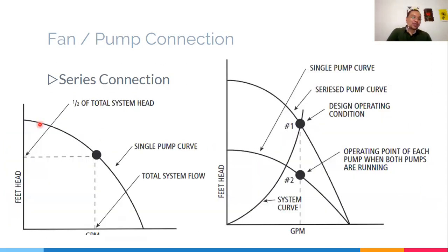All right. So again, this would happen if you are looking at the performance curve of our unit, no? This is a single unit. Ito yung pressure performance niya, ito yung flow performance niya. If you put two units in series, this is what would happen. From this one, your system curve becomes this one. So kabaliktaran ng una, no? If you put equipment in series, your flow remains the same, but your head increases.